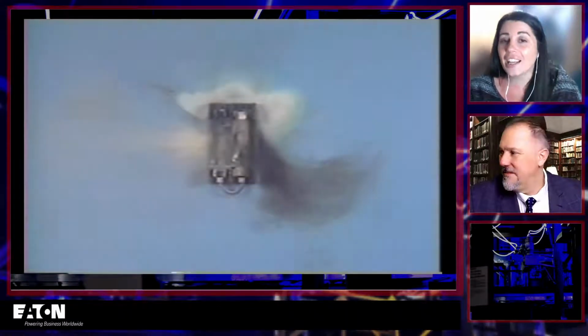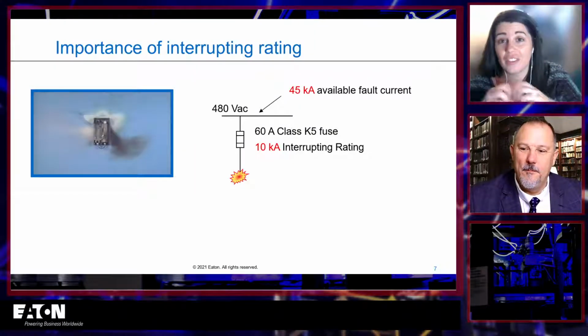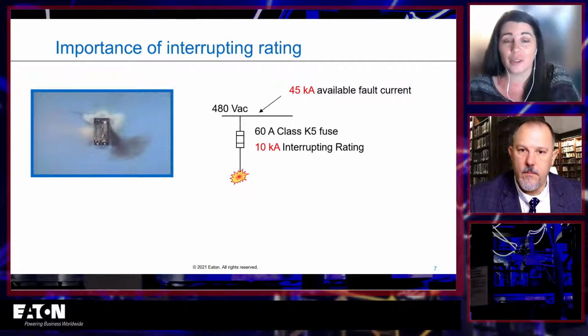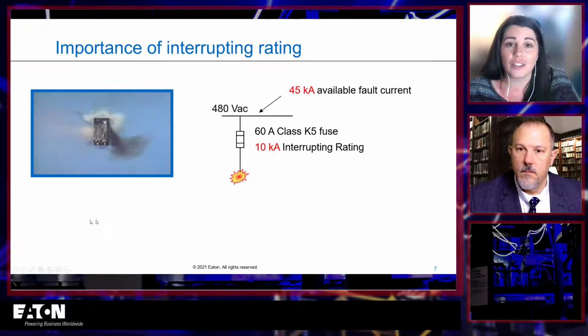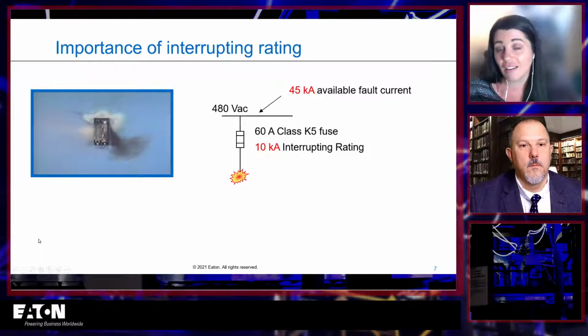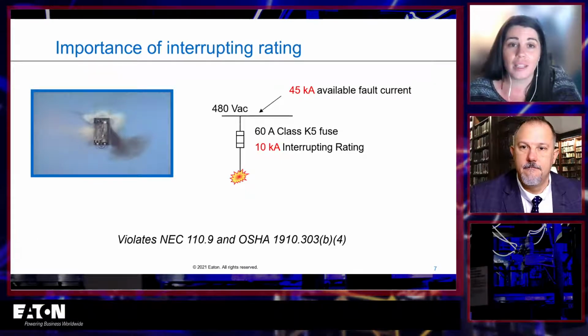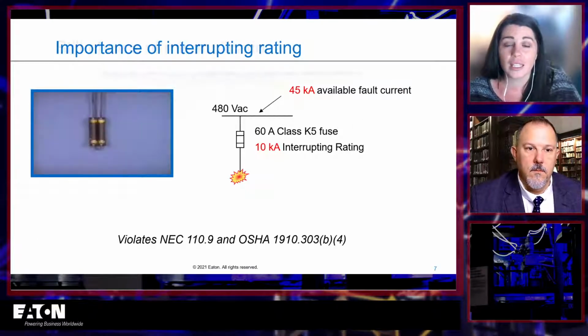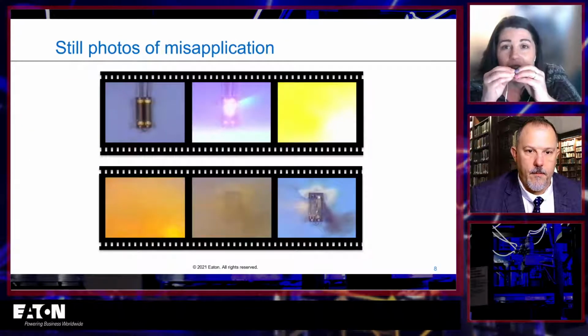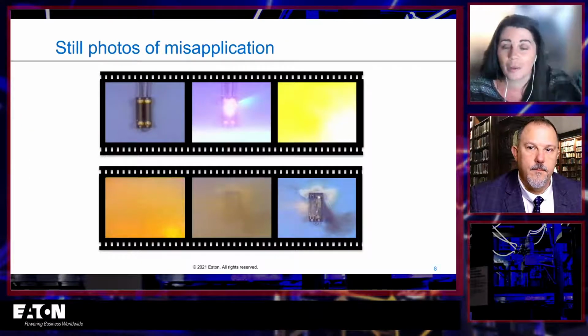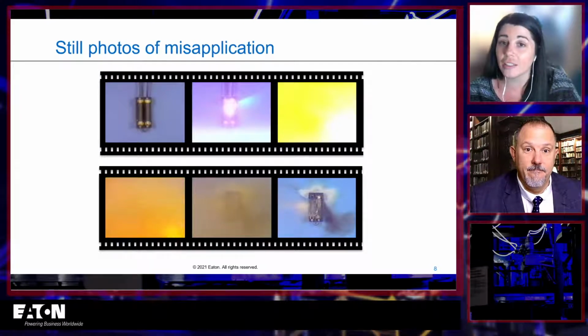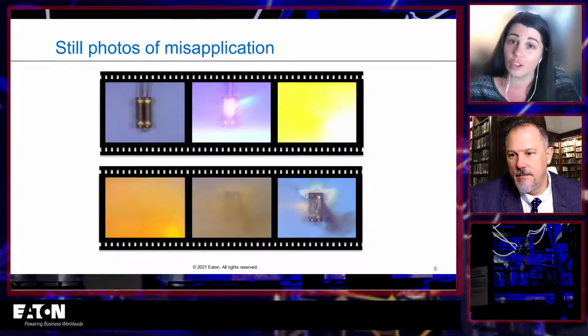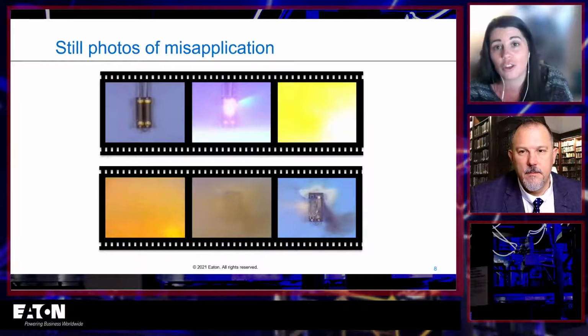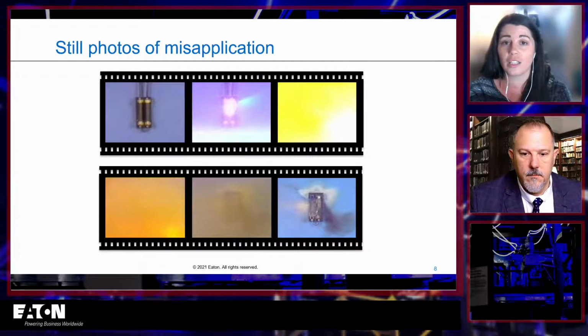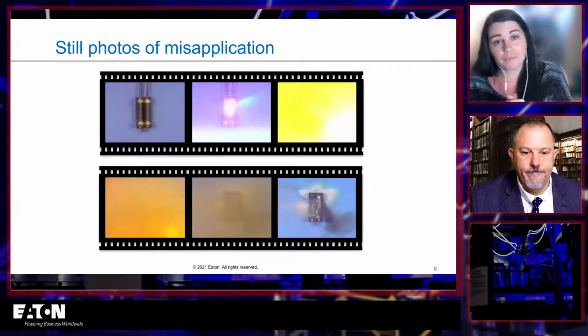So more or less the same result here. A little bit less debris. You just don't have the molded case frame to fly all over the place. But this is also, you'll see, a violation of 110.9 and OSHA. In the little still frames on the next slide, you can see that hot spot that just turns into a big old kaboom here. So it knows there's too much current, it melts, but there's too much arc, too much energy in that arc, it's not able to extinguish it safely.